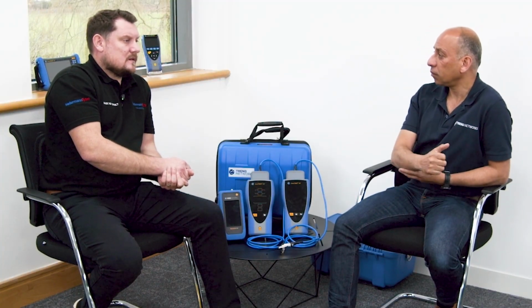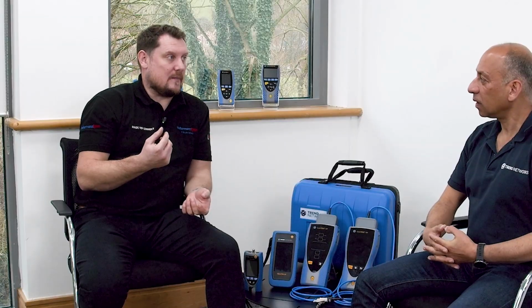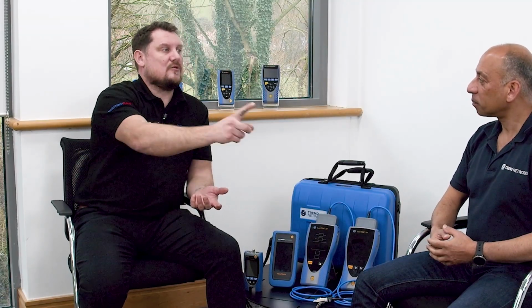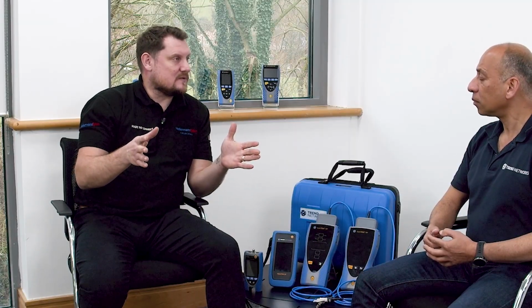You would normally have some form of fiber loop storage. It's as simple as that, like a J run. The best way to describe it is trying to store that excess somewhere. What you don't want to see is it coiled up underneath cabinets or on top of cabinets, but instead building a proper system and solution to actually store that fiber loop. If we use a product like the HellermannTyton GigaDuct, you can use extra bends to create a fiber loop storage as part of that cable management system, or use products that look like 19-inch mounted panels, bringing fiber in there to store looped fiber within that.